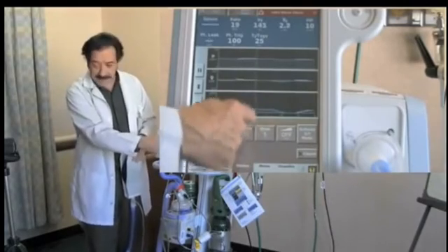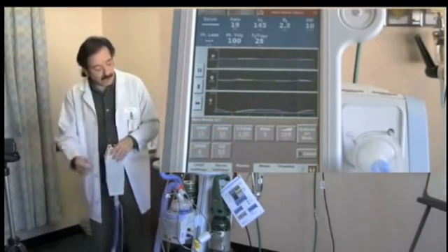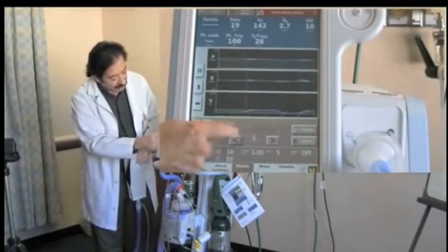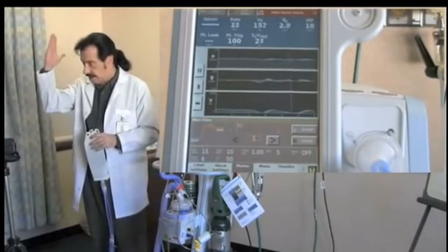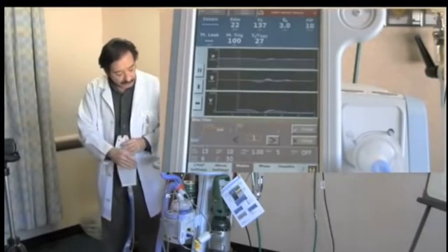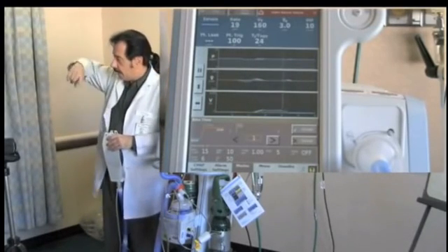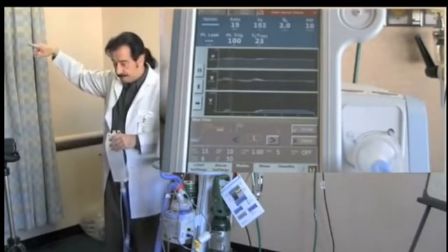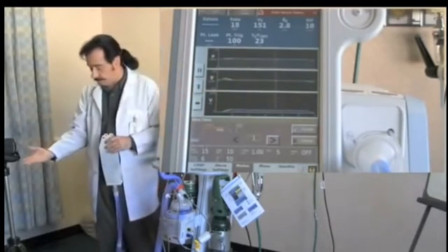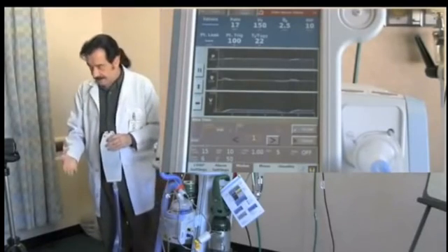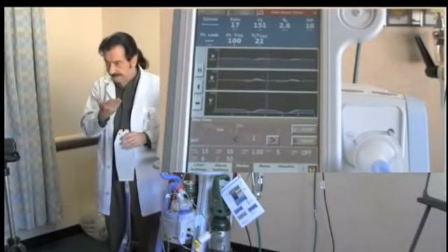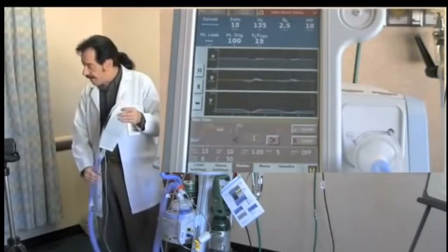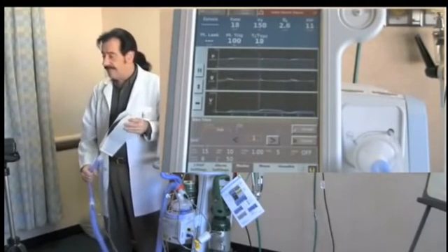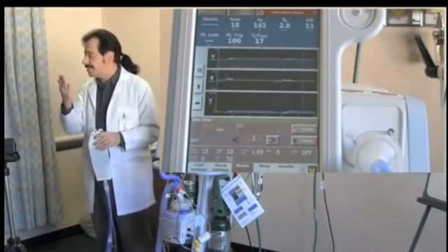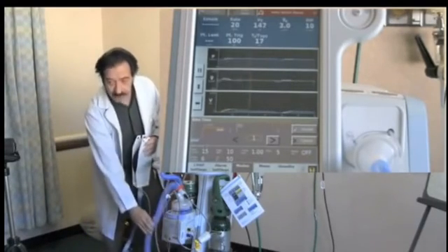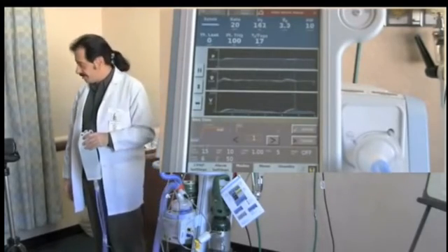There's a rise here. Rise is like C-flex in reverse, so with that active, I can turn that to 1, which is the fastest rise time for the inspiratory flow, meaning that the flow comes in really fast to get the airway pressure up to the IPAP level as quickly as possible. So that would be a square pressure waveform, okay? If the I time is kind of short and the IPAP is set fairly high, then the flow has to be so fast to get that in that it can get kind of physical to the patient. It's kind of like it's slapping them with flow. Sometimes you can even see the inspiratory limb jerk, okay? Probably not a good situation.